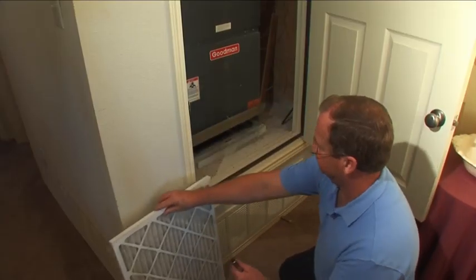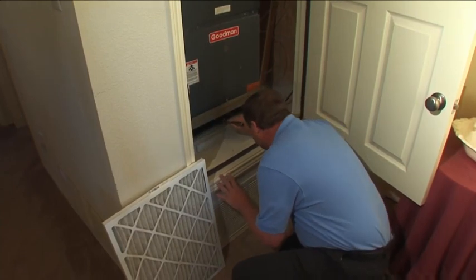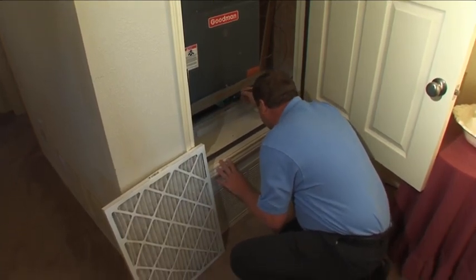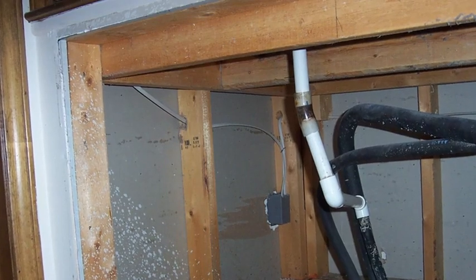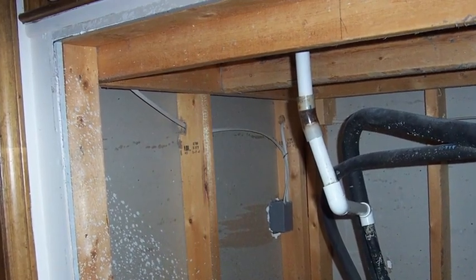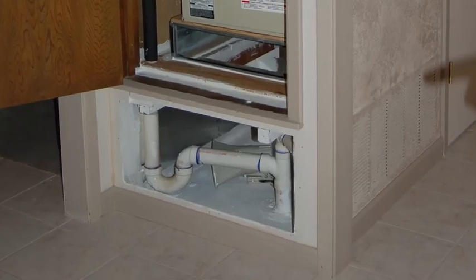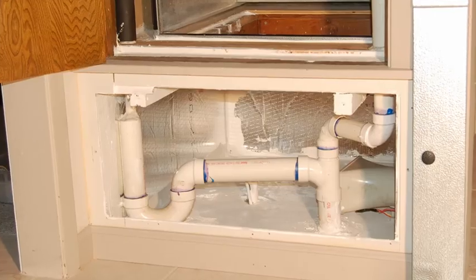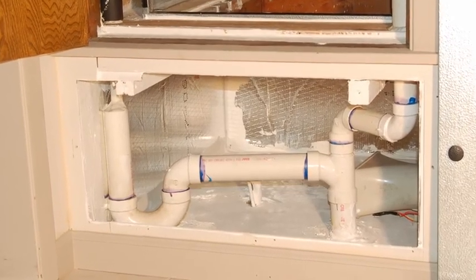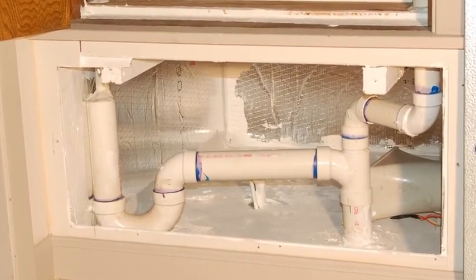Another common one in the Sunbelt and in some condos and apartments up in the frost belt is when return grills feed into an open box cavity under an upflow furnace or air handler sitting on a plywood platform, in a closet or in a garage. These tend to be readily sealable, either by hand or with AeroSeal. Over the years, I've crawled into many of these and sealed them up with mastic and ductboard.